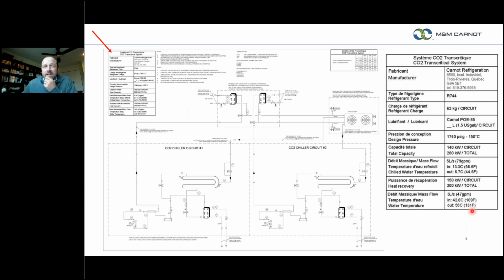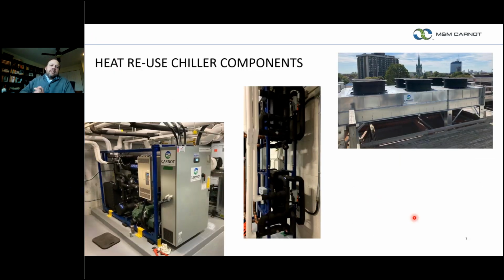So this was a sweet spot for us, because we were able to give you a little bit more heating than we could give you cooling, with the compressor heat rejection that was added to the CO2 loop. But these heat exchangers up here, I'm showing in the picture in the middle. This is the difference that you would see between a normal CO2 based chiller and one that has heat reclaim. It's not as good of a picture as I would have liked to show you, but it was one that I was able to take with my telephone when I was up there a couple of months ago. These are two heat exchangers, one for each circuit. The CO2 comes into that heat exchanger, and I can reject heat into that loop, or I can reject heat out into the roof. So this is the latest design of a small chiller that we have for a building.